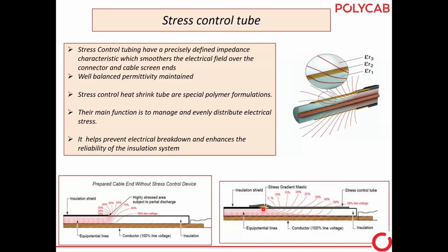Generally, up to 66 kV, we use heat shrink stress control tubes, but above 66 kV, there are semi-molded stress controls. Silicon-based molded stress control or cold shrink stress control tubes are there. Basically, the proper word is stress cones.